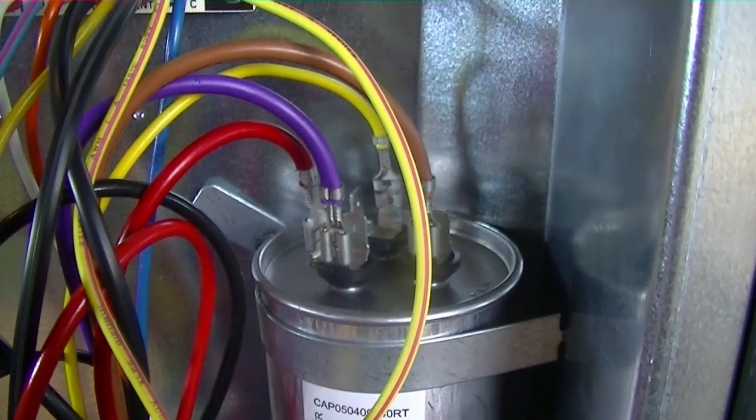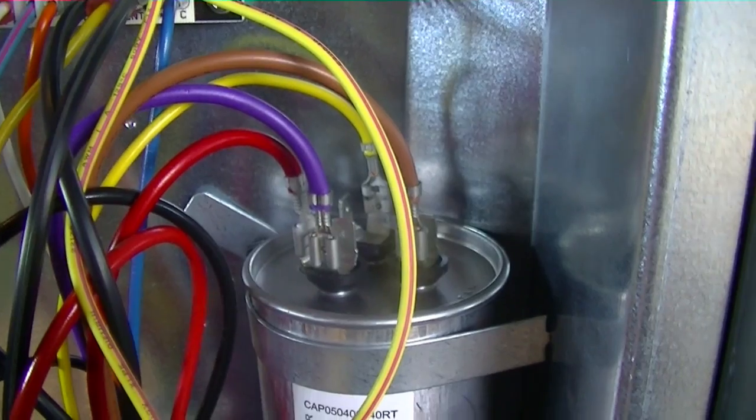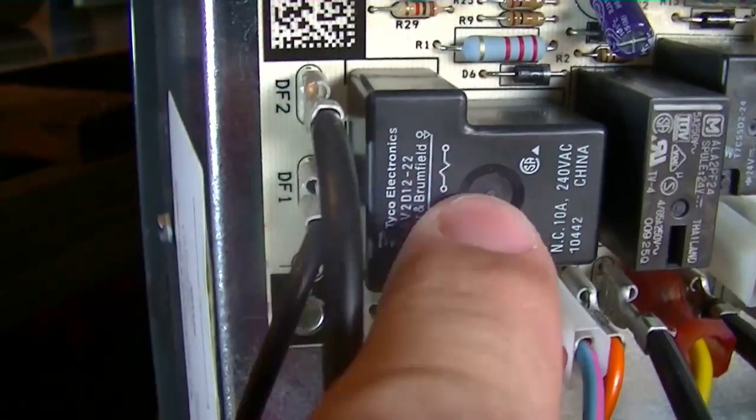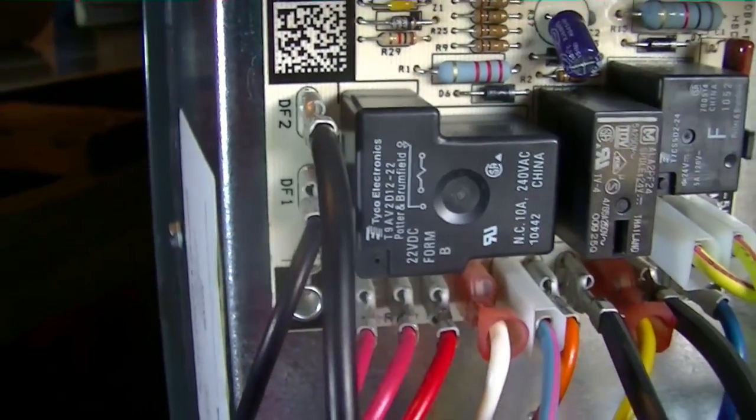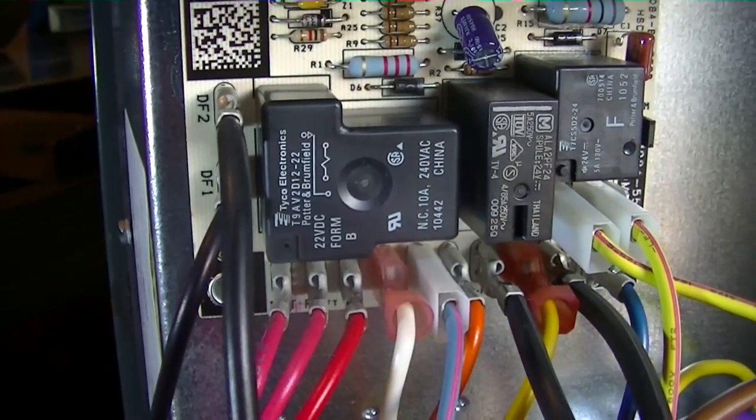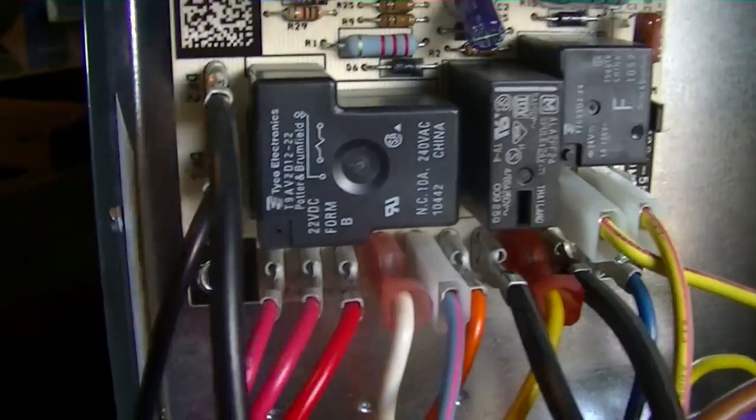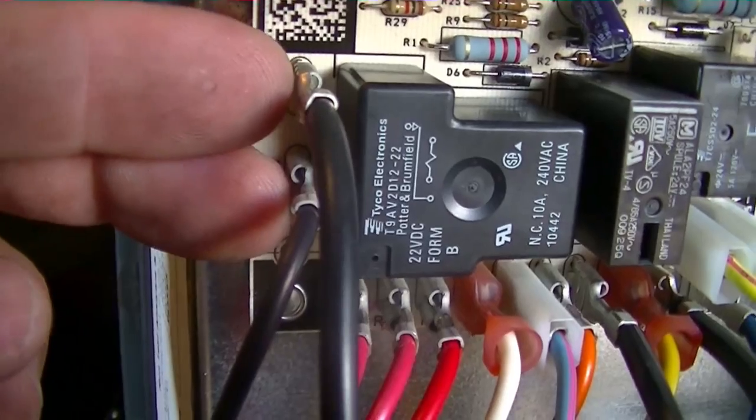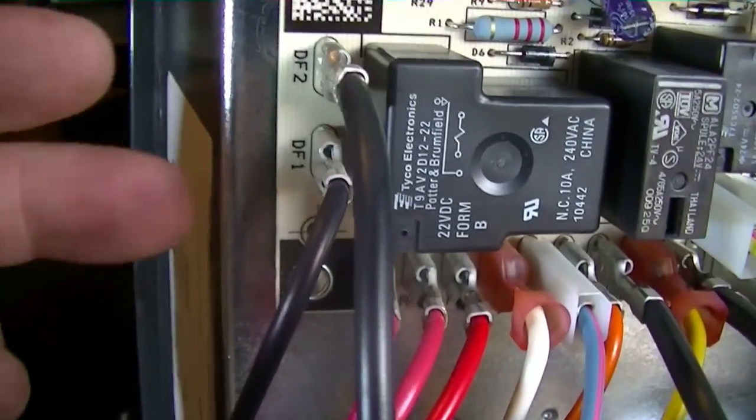The black, which is the common for the fan motor itself, actually heads to the defrost board where it can be shut off by this relay. This defrost relay can shut the fan off when the system is in defrost. And that's why that particular wire goes through there. It can be broken in between those two points.